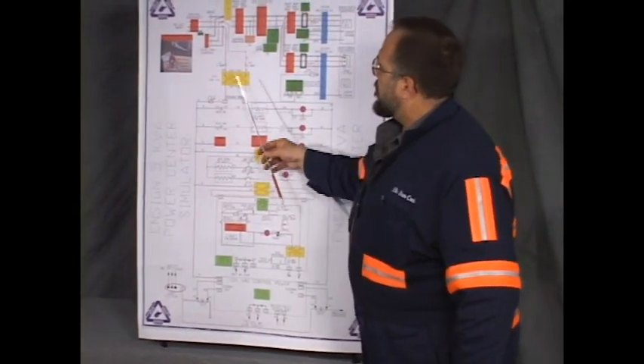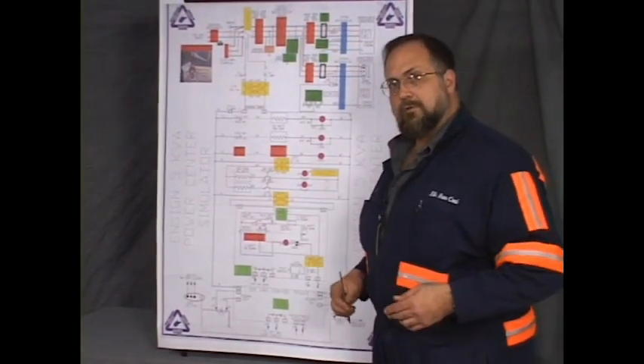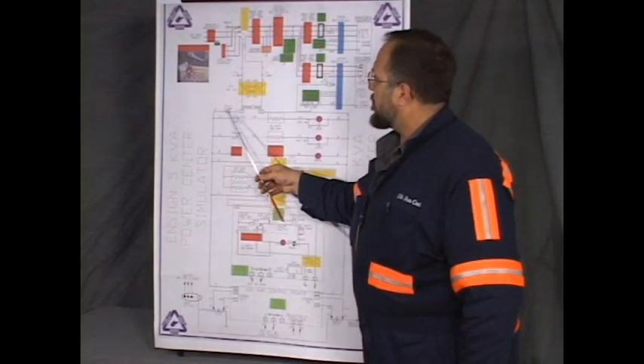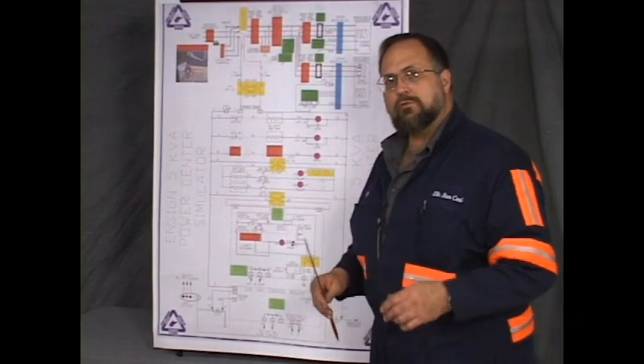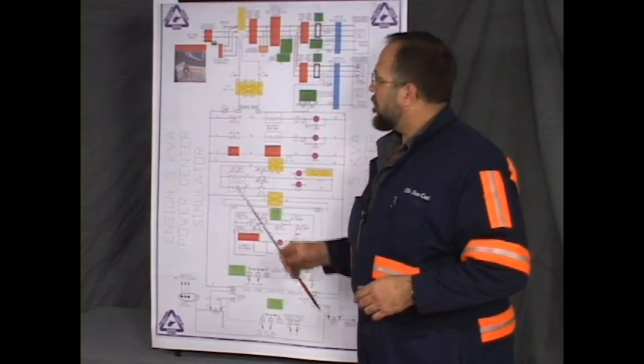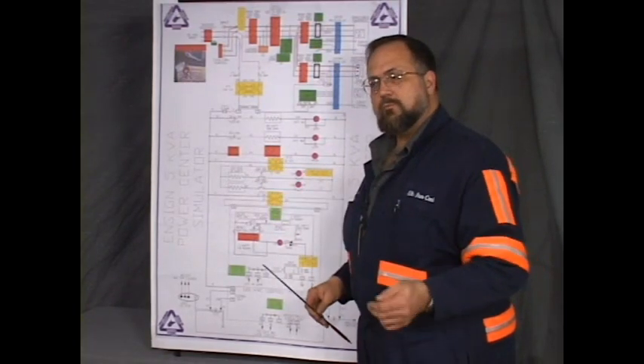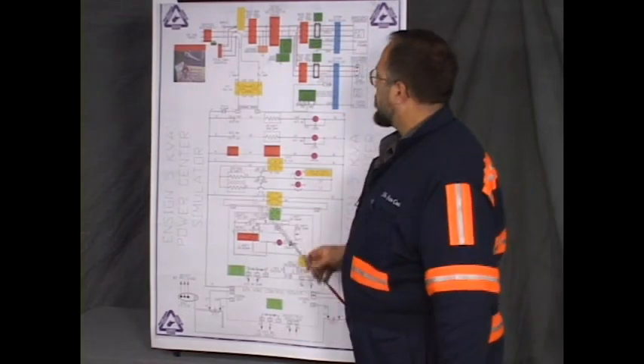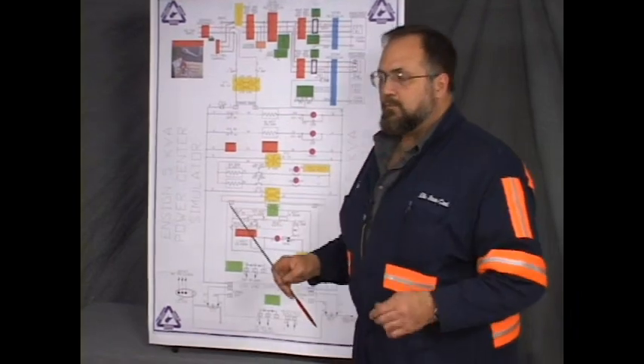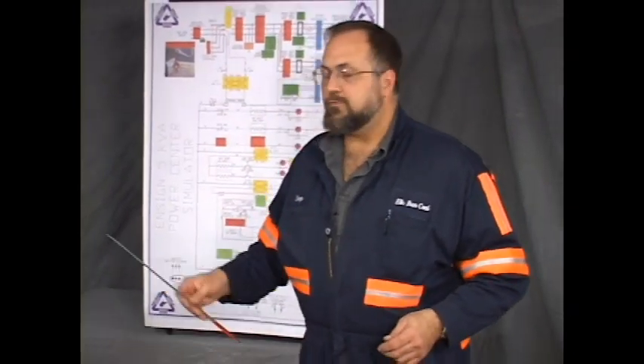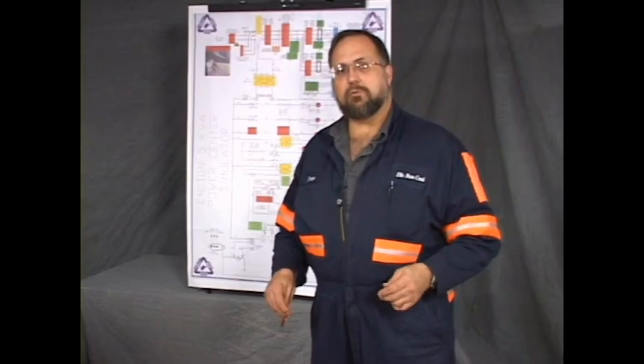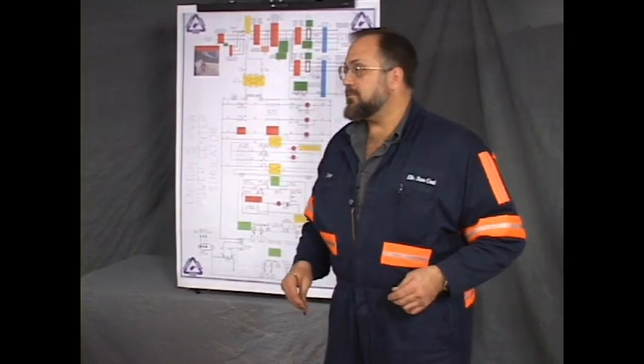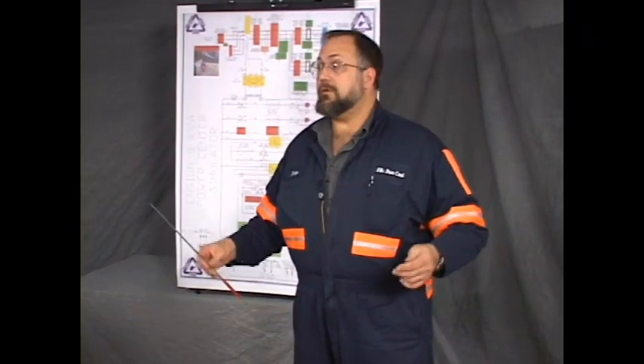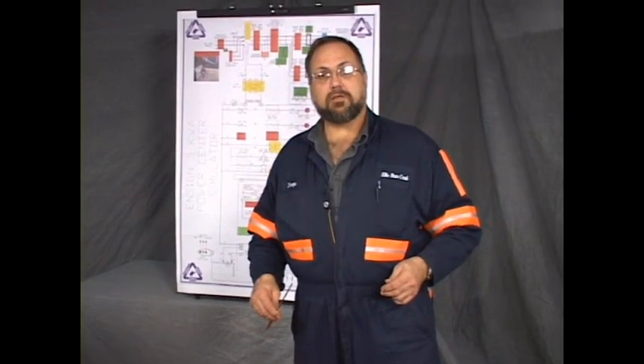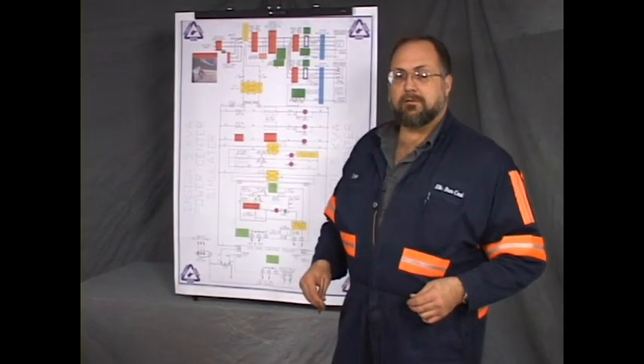When you're troubleshooting, use the print just like a road map. Have little destinations. Check from point to point, line to line. Each wire has two ends. Move from one end to the other for continuity. Read the print. If you can read the print and you can read your meter, there's no problem that you can't find. Doesn't matter whether it be a power center simulator, a power center underground, any other electrical circuits you choose to check. There's nothing you can't find. And that's all I have.